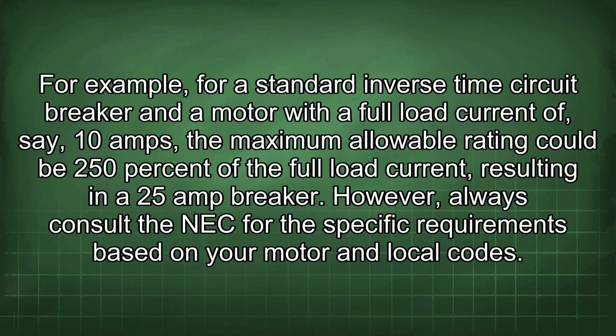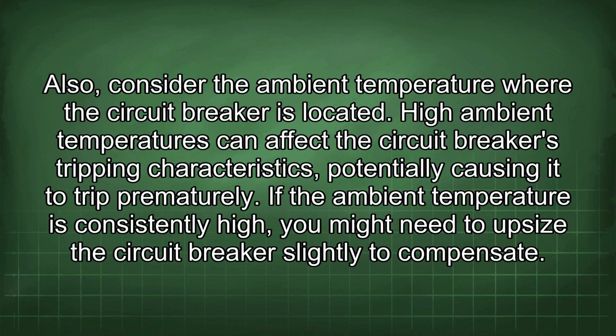For example, for a standard inverse time circuit breaker and a motor with a full load current of, say, 10 amps, the maximum allowable rating could be 250% of the full load current, resulting in a 25 amp breaker. However, always consult the NEC for the specific requirements based on your motor and local codes. Also, consider the ambient temperature where the circuit breaker is located. High ambient temperatures can affect the circuit breaker's tripping characteristics, potentially causing it to trip prematurely. If the ambient temperature is consistently high, you might need to upsize the circuit breaker slightly to compensate.